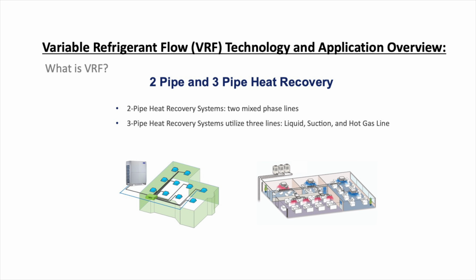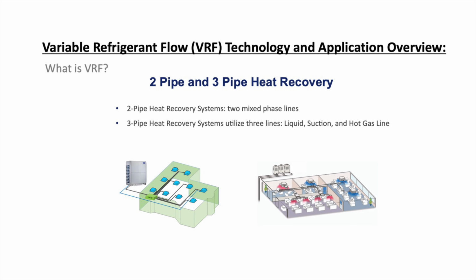In a 2-pipe heat recovery system, you have two mixed phase lines. Currently, there are two manufacturers that I know of that use this technology. You have Trane Mitsubishi and you have Carrier. And you also have 3-pipe heat recovery, which uses 3 refrigerant lines. You have a liquid line, a suction line, and a hot gas line. Manufacturers that use this technology are Daikin, LG, Toshiba Carrier, and Samsung.